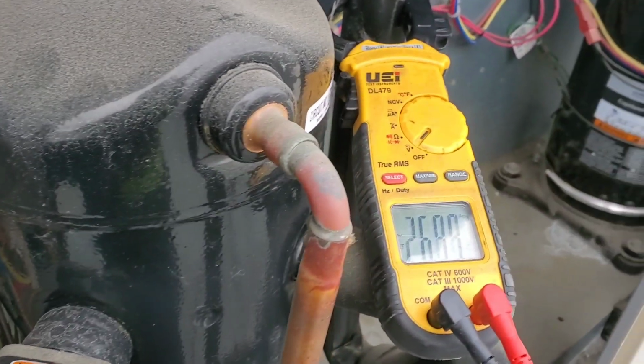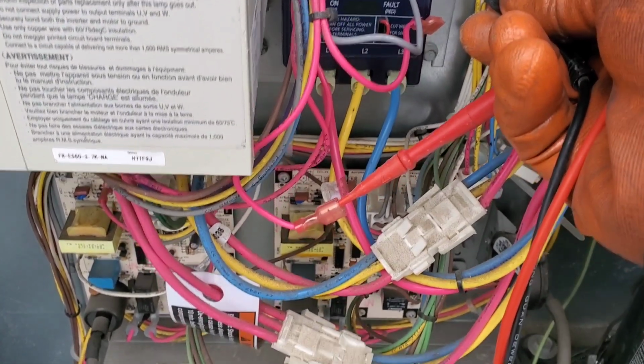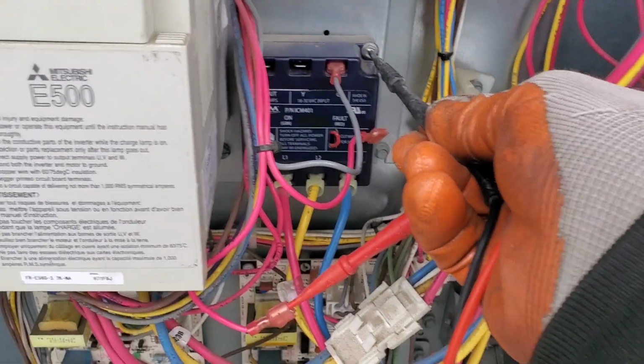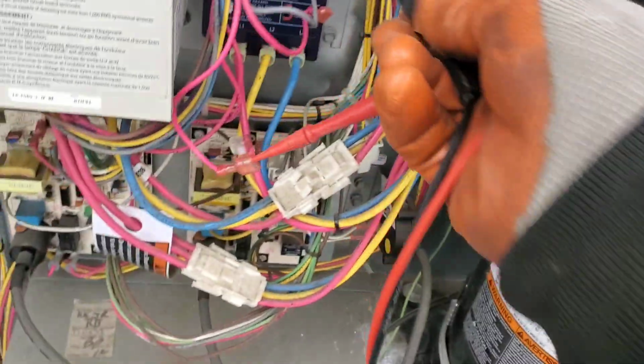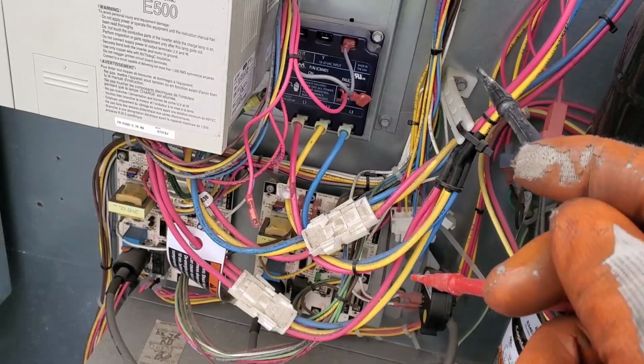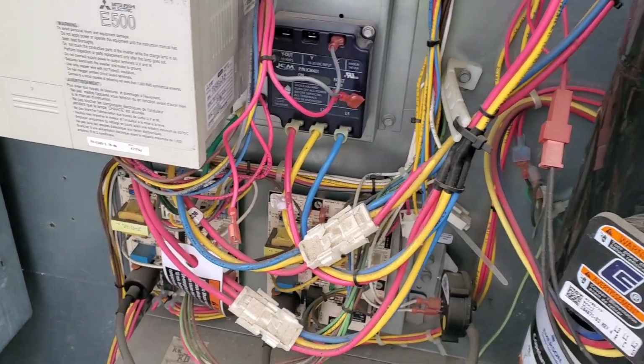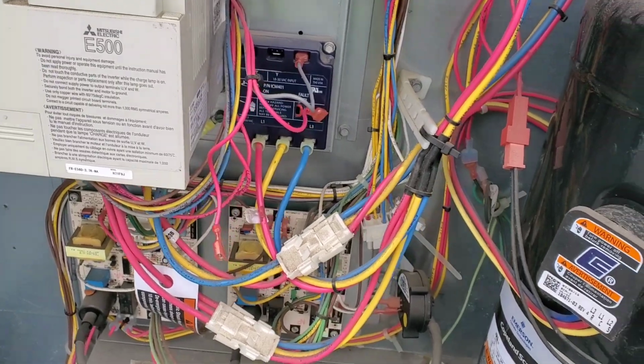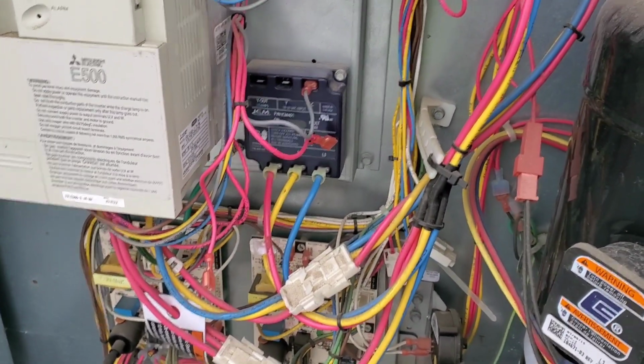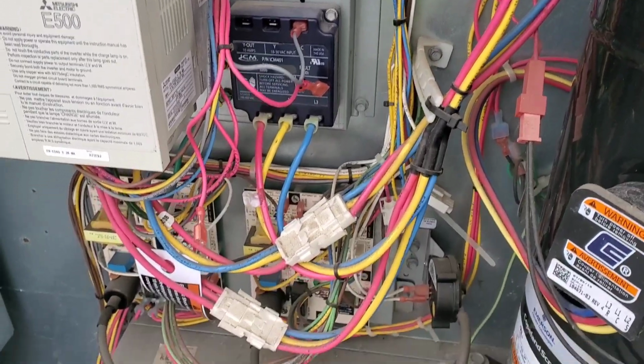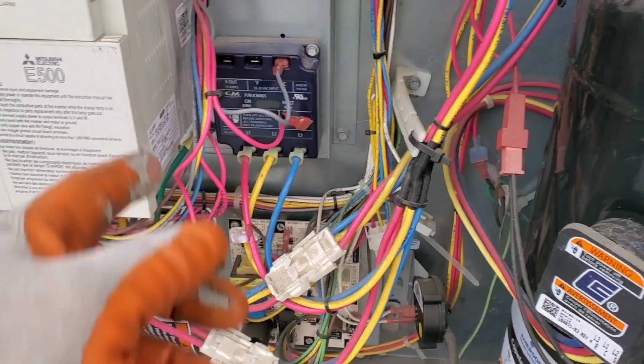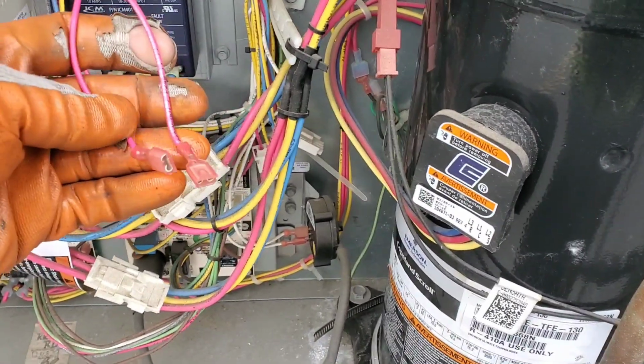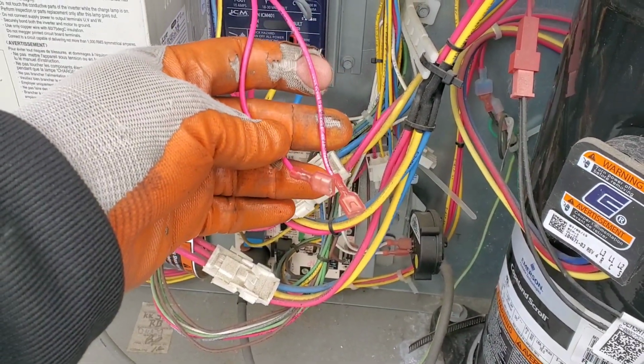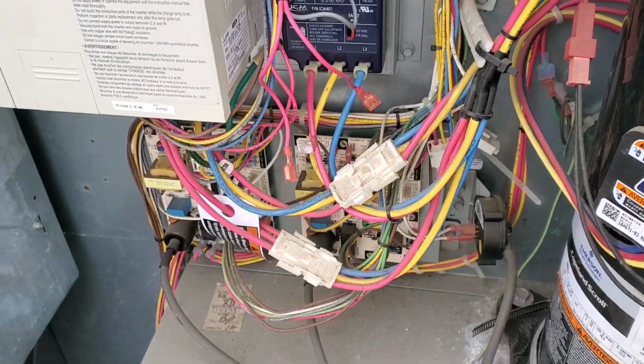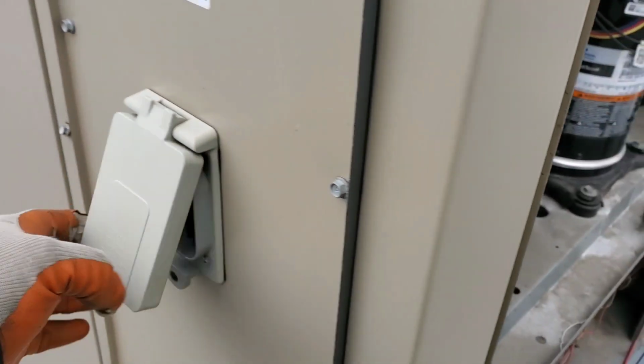Okay, so if we check the multimeter, we have 26.1 on this Y in, and on the ground, so we have 26. So this device is bad. We have to replace it, and we can also bypass this device just to check, but this is not much expensive, so we're gonna replace it. So let's test it with bypassing this device. So we have to put a jumper in between those two wires just to test. Okay, so turn off the power supply first.